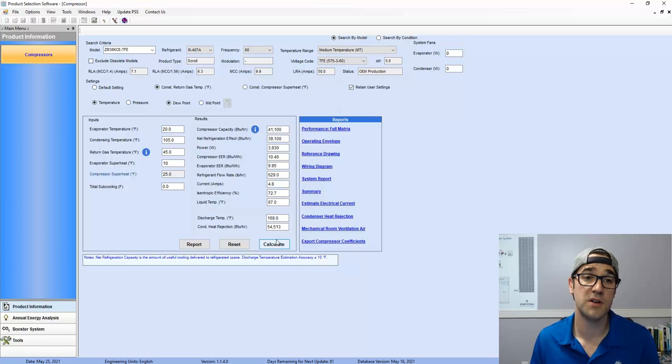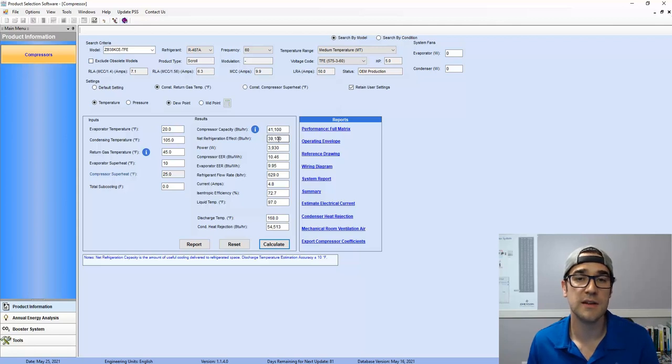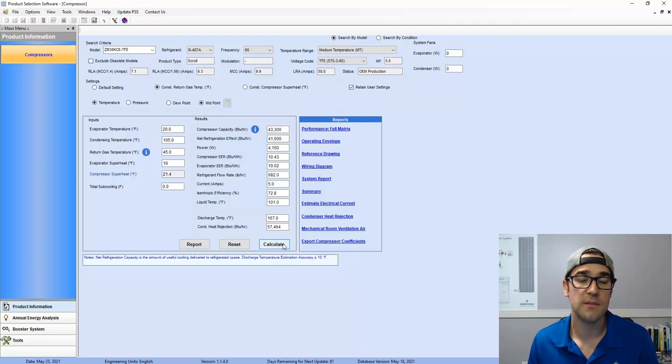Well, now our compressor capacity is 41,000, but our net refrigeration effect is 39. So this is on the dew point. But if you size it to the midpoint, bang.